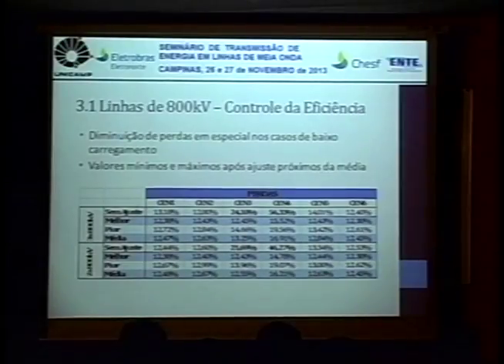So in all the scenarios, considering a corridor with 2 800 kV line, we could decrease losses when compared to the case we called case with no adjustments. So this is the initial conclusion. We cannot operate half wavelength line without the characteristic power, especially with low loads. Otherwise, you're going to have great losses.